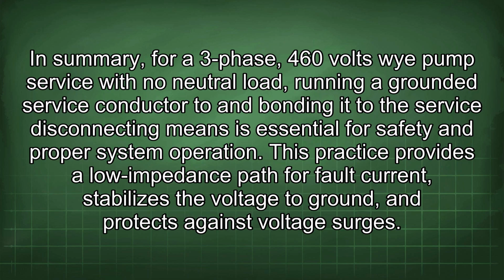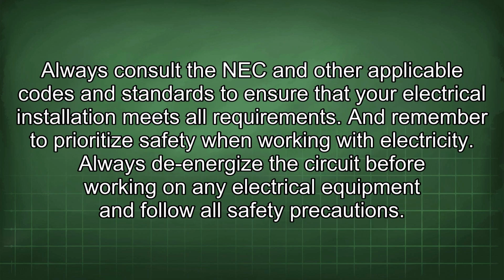In summary, for a 3-phase, 460 volts Y pump service with no neutral load, running a grounded service conductor and bonding it to the service disconnecting means is essential for safety and proper system operation. This practice provides a low impedance path for fault current, stabilizes the voltage to ground, and protects against voltage surges. Always consult the NEC and other applicable codes and standards to ensure that your electrical installation meets all requirements.